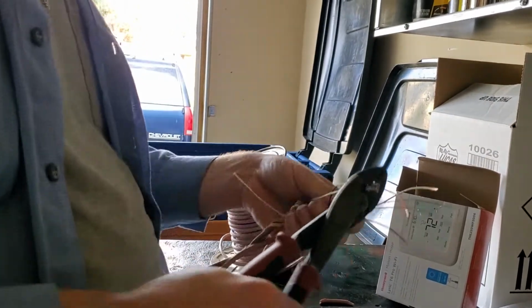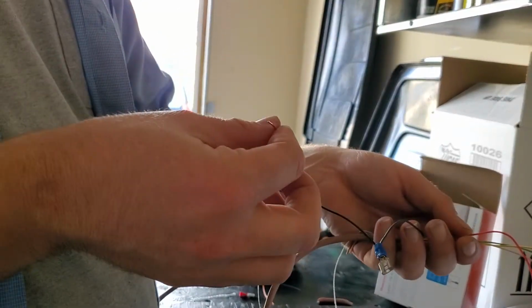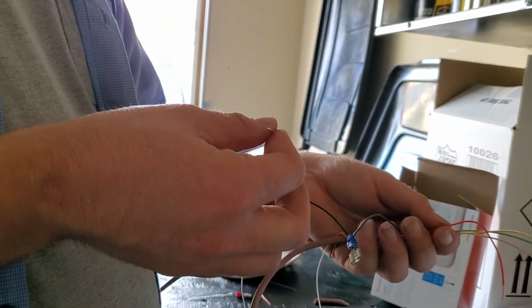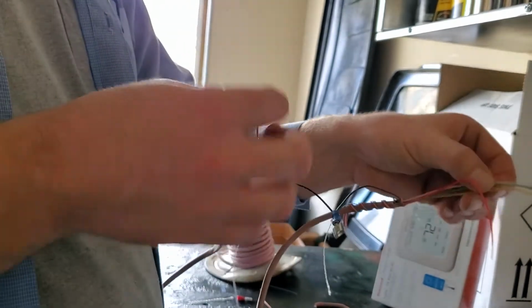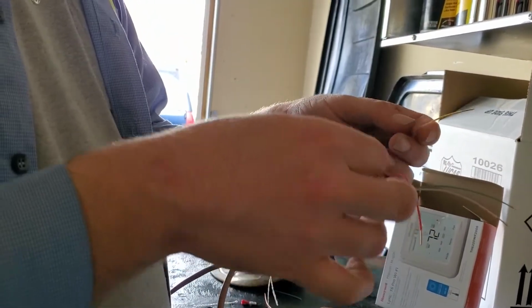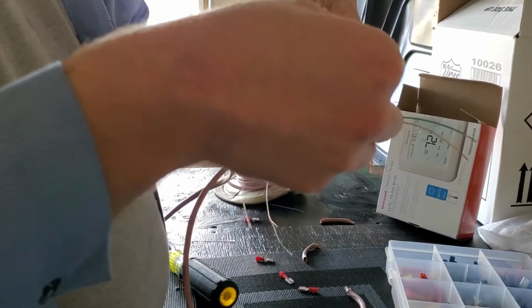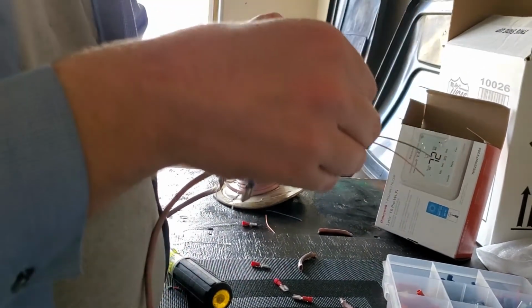I'm gonna put these commons together. This is going to my condenser, right? Right, whenever cooling is energized, whenever Y is energized, I want the condenser to energize. So we're gonna jump these out.